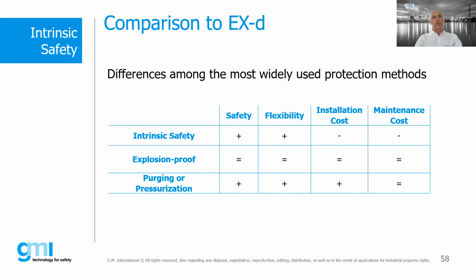We want to now give you more overview about the EX protection methods. If you look at explosion proof, where you have a certain safety, certain flexibility, certain installation cost and maintenance cost, we want to highlight that intrinsic safety is more safe because we are reducing the energy, we're more flexible, and installation and maintenance costs are lower than explosion proof. And also it is the only technology that allows live maintenance without disconnecting the power from the system.